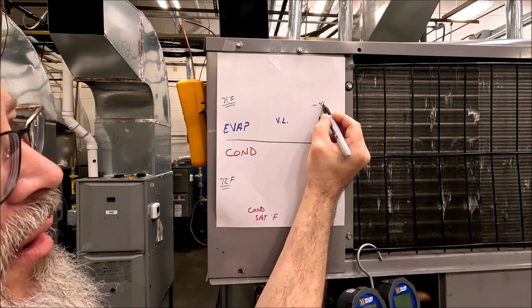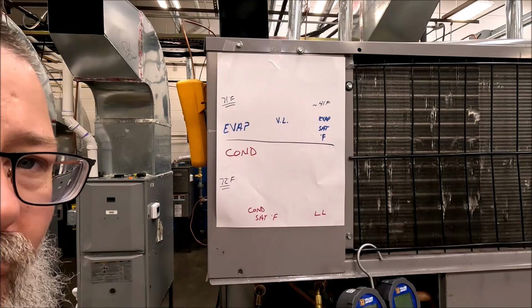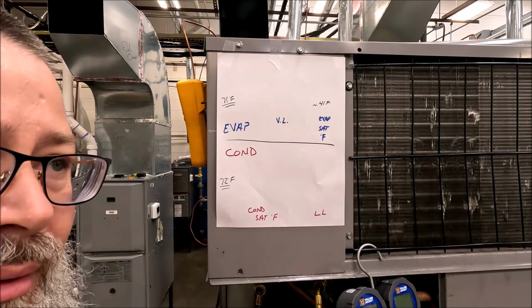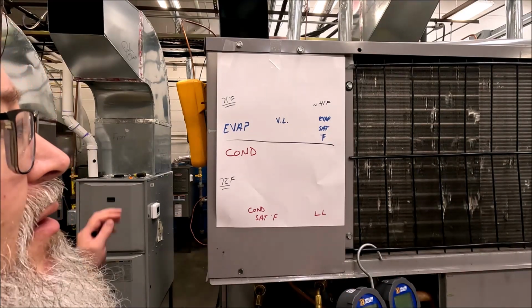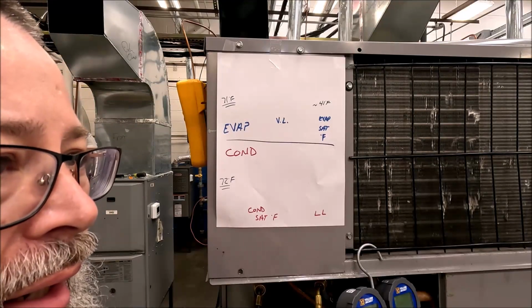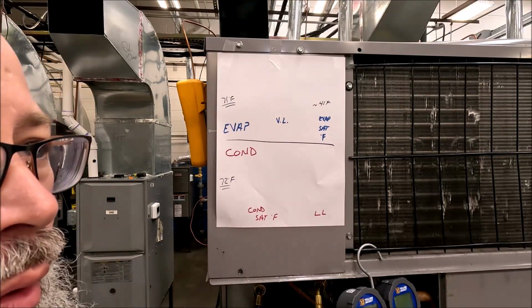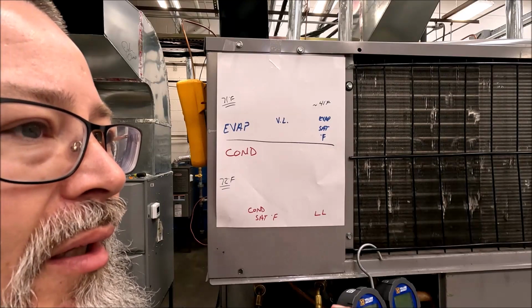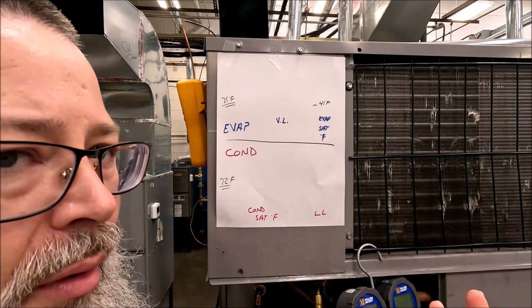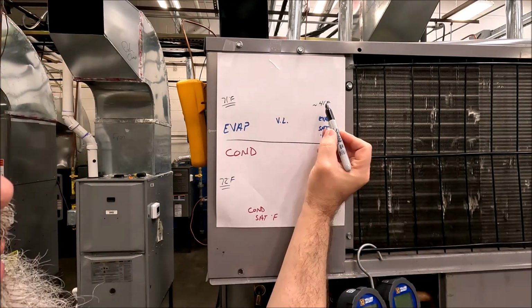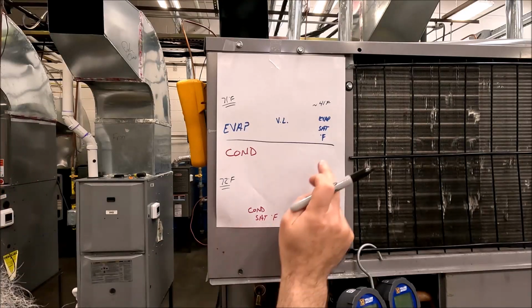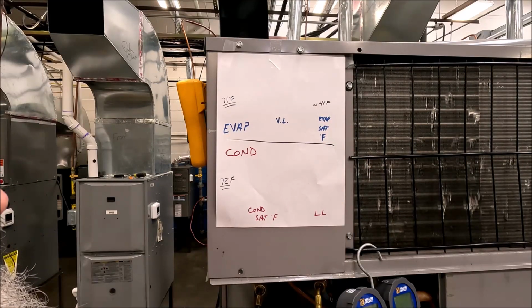So I should be somewhere around a 41 degree coil, the saturation point, okay? That is where the heat from that 71 degree return air is going across that evaporator coil, and we're changing state from a liquid to a vapor, okay? So I should have about a 41 degree evaporator saturation temperature.